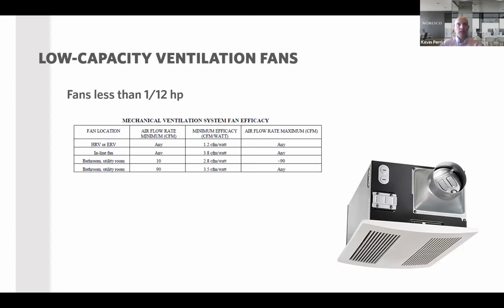Low capacity ventilation fans. I look at this as maybe bath fans. So fans that are less than 1/12 horsepower now have to follow this table. If you're familiar with the City and County of Denver amendments from last year, this is the exact same table that they adopted. So if you're familiar with that, nothing has changed. If you're not familiar with that, I would say get familiar with this table, because now you have minimum efficiencies on these low capacity fans. Now there are exceptions. If fans are components of a listed heating or cooling appliance, or a dryer exhaust or domestic kitchen range hood, those would be exempt from this.